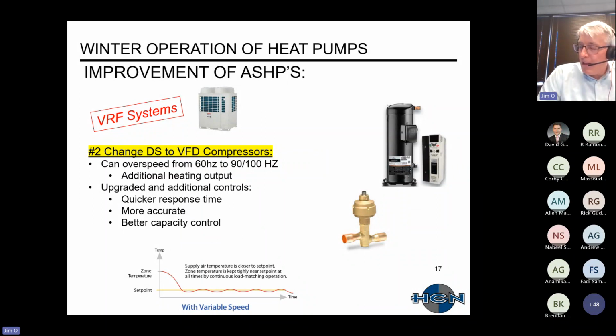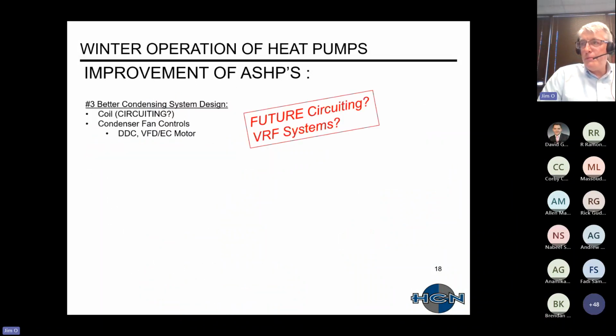And then there's this enormous electronic expansion valve that really isn't that big, but I just wanted to make it bigger, since you're changing from a thermal expansion valve to an electronic expansion valve associated with the VFD compressor. Next two items, the first one that I kind of minimized is they're putting in better condensing system design. In my mind, once again from the VRF systems, they typically have smaller tonnages for their condensing systems, from like 6 up to 14 tons. And what they end up doing to reduce the defrost is that they provide additional circuiting on their condenser coils.